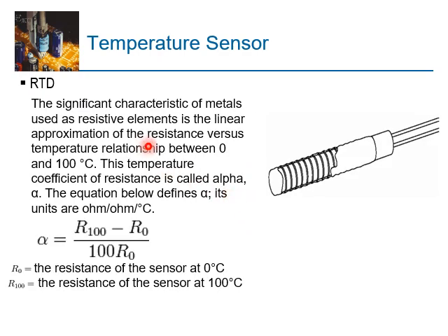You also have the RTD, which basically changes its resistance value as the temperature changes. That is because of the metallic property: higher temperature causes more disturbance in the current flow, so the resistance increases, and you can have this type of sensor calibrated for temperature change.